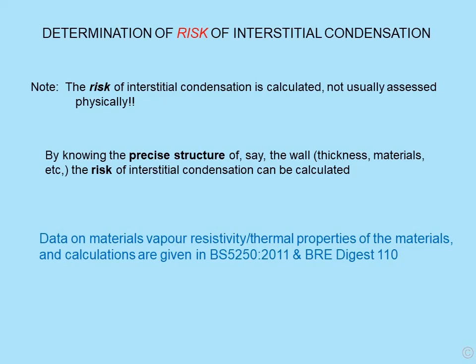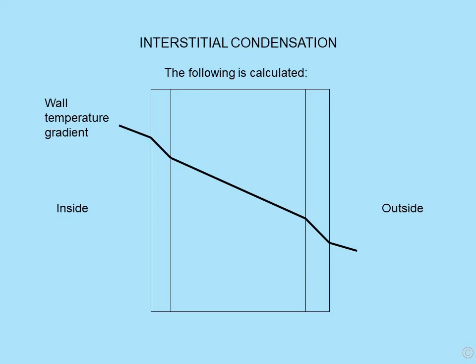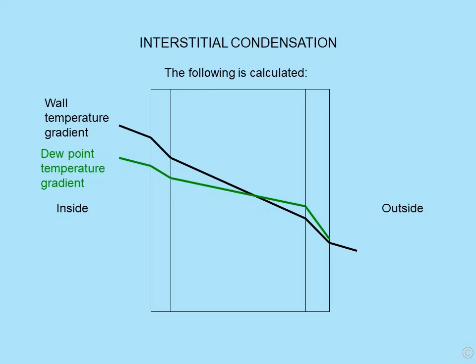The risk of interstitial condensation is calculated rather than assessed physically, using data on the precise structure of the wall — its materials and thickness. Data on vapor resistivity is given in British Standard 5250:2011 and Building Research Digest 110. By entering figures into equations knowing the wall construction, we can calculate a wall temperature gradient and a dew point temperature gradient through the wall. If those two gradients cross, we get interstitial condensation.